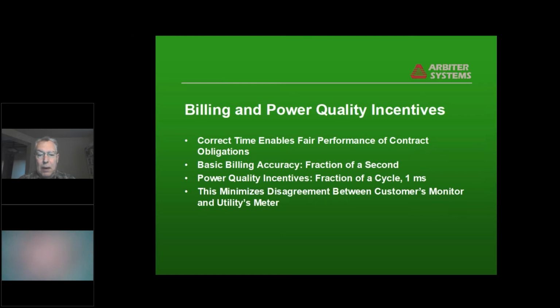For billing and power quality incentives, basic accuracy, a fraction of a second is probably okay. But for power quality incentives, in order to look at the actual effects on the waveform that are being imposed by a customer's load, it needs to be more accurate than that, in order to make sure that the harmonic and other information agrees between the customer and the utility.